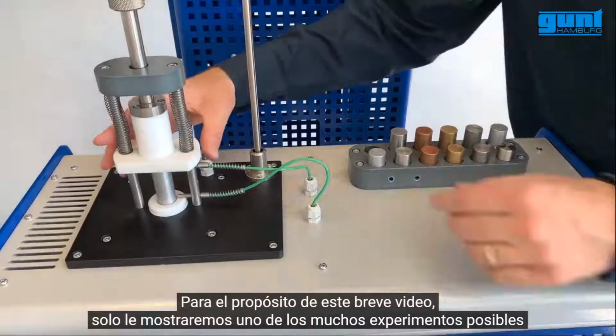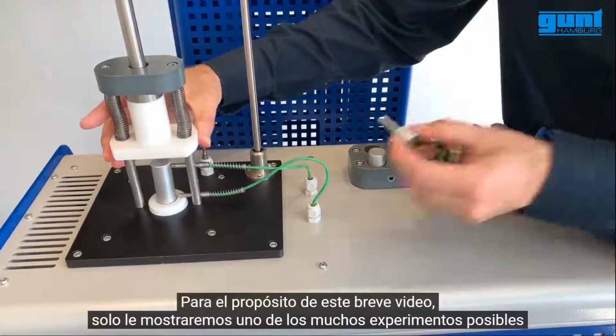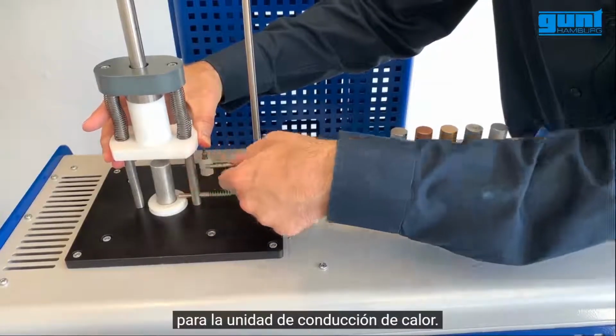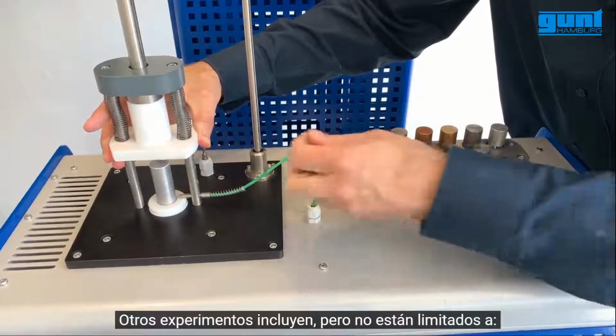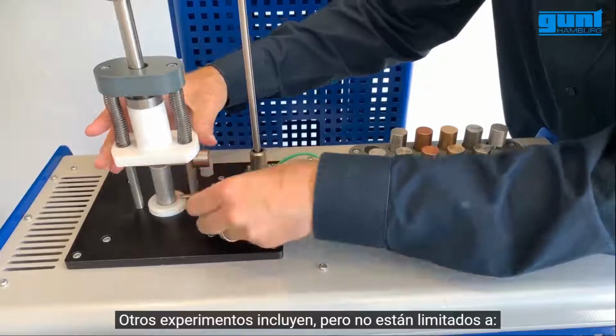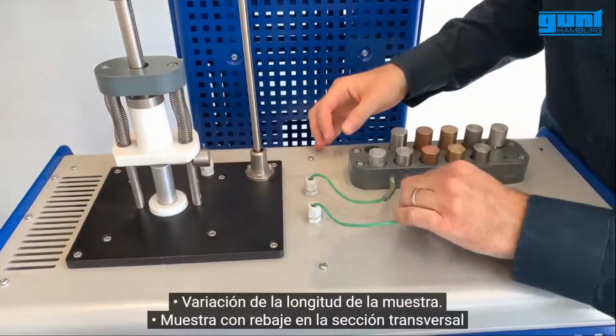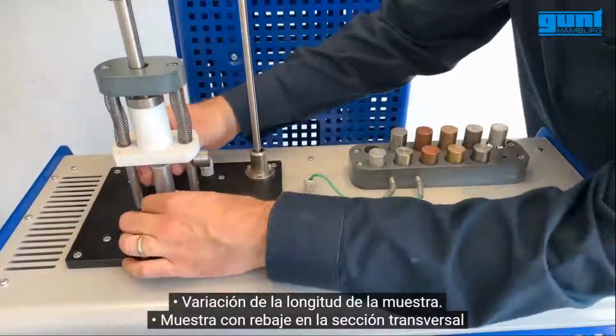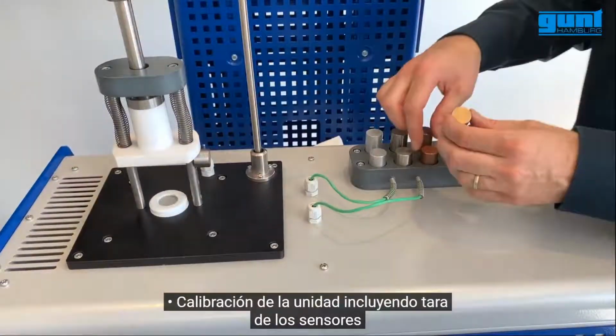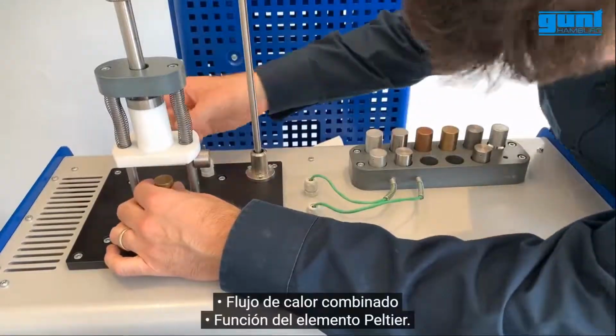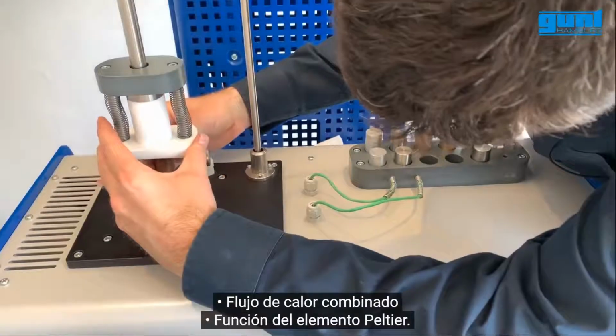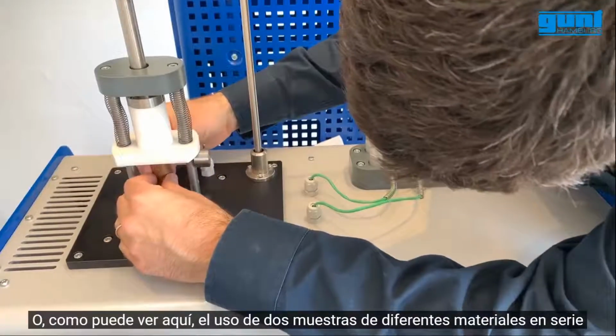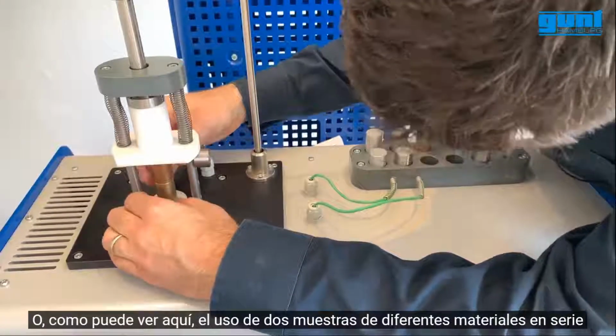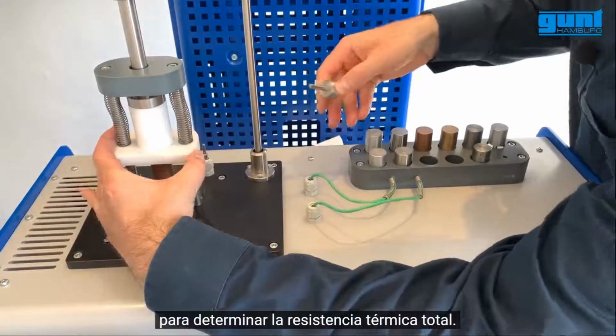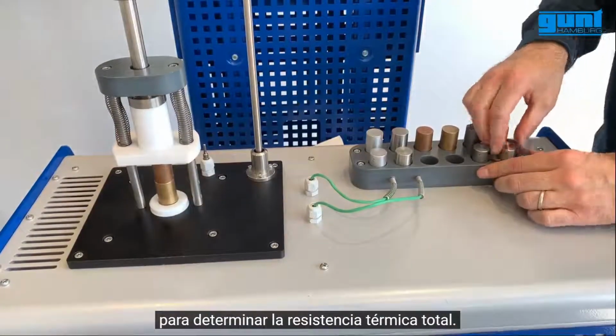For the purpose of this short video, we have only shown you one of the many experiments for the heat conduction unit. Other experiments include, but are not limited to, variation of specimen length, sample with recess in cross-section, calibration of the unit including taring of the sensors, combined heat flux, function of the Peltier element, or, as you can see here, stacking of two specimens of different materials in order to determine total thermal resistance.